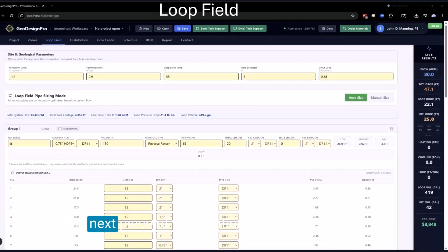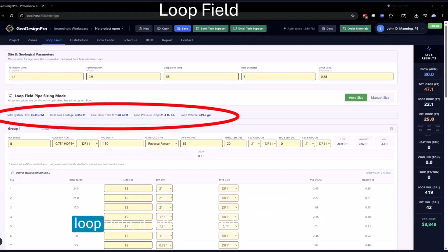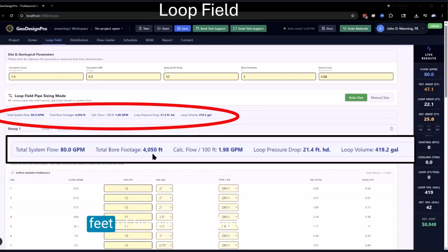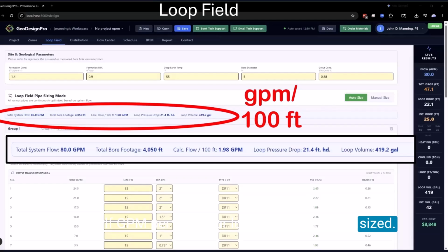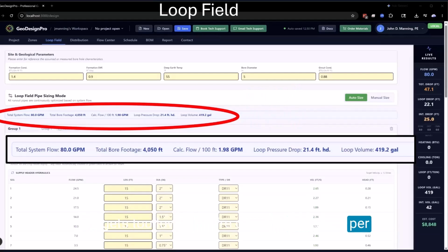The next piece of information you get is this summary of loop data. It tells you the total flow rate, how many feet of bore in total, and the GPM per 100 feet of bore. This is a parameter I've gotten used to looking at. I would say if that's between 1.5 and 2.5 GPM per 100 feet, your loop field is properly sized. If you're down to 1 GPM per 100 feet, chances are the loop field is oversized. If you get up to 3 or 4 GPM per 100 feet, chances are the loop field is undersized. So it's sort of a sanity check. It gives you the loop pressure drop and the internal volume of the loop field. And over on the right, we try to keep a running tab of some of these key parameters.